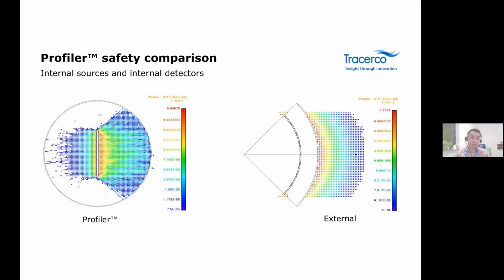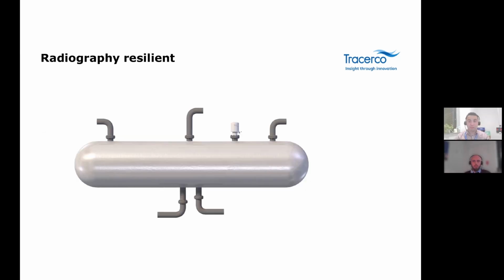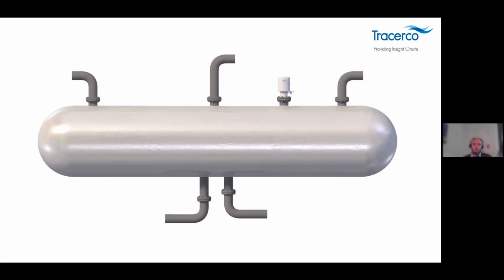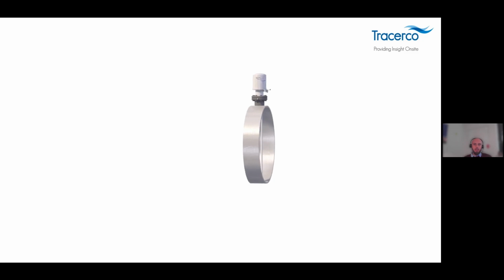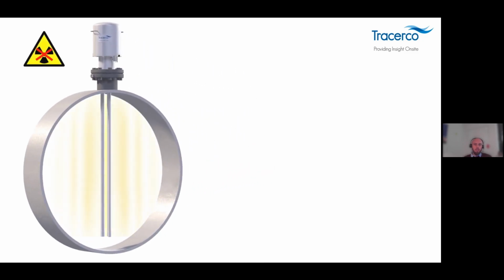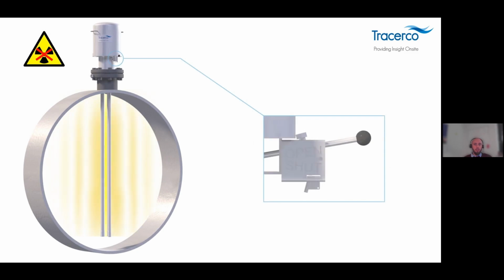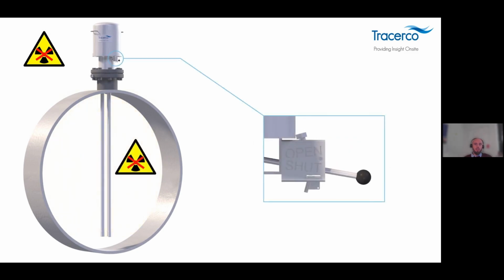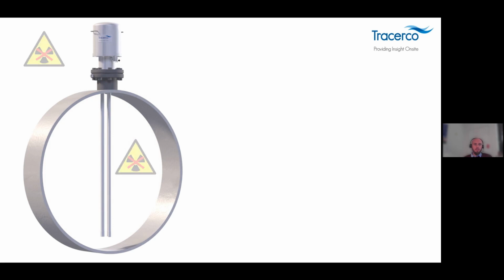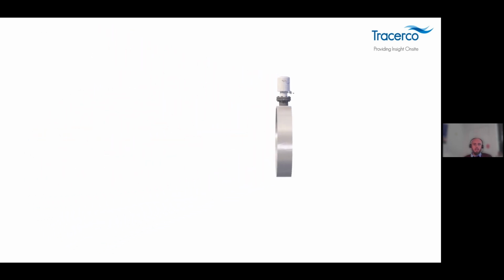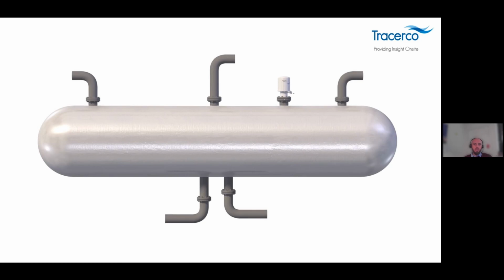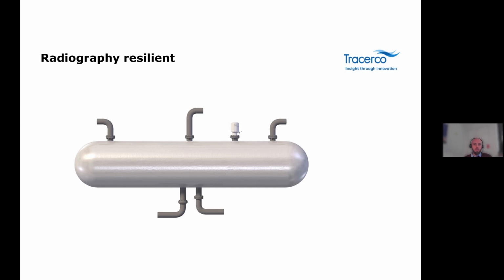It's up to Oliver to talk about the other aspects of the profiler. So the profiler is radiography resilient as well, and the collimation of the profiler has a positive effect on this. If vessel entry is required, there's an isolation handle that pulls the sources out of collimated alignment to shield them for safe entry to perform cleaning or maintenance, as demonstrated in that short animation. As the instrument is internally mounted, there is no radiation measurable on the vessel wall from the profiler, and that's due to the low activity of the gamma sources that we use. These do not have enough energy to penetrate the process fluids other than what we need and want for the measurement.